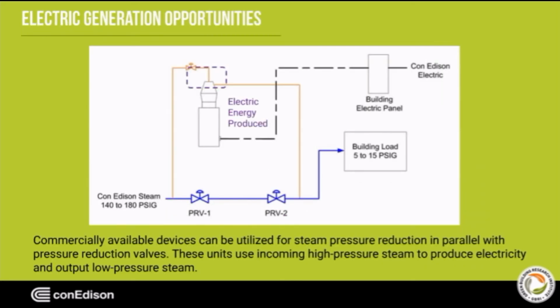As you can see here, these systems will be installed in parallel to your pressure-reducing valves. When these systems are running, the PRVs are bypassed and electric power is produced, and low-pressure steam needs are provided to the building. Overall, these systems are meant to provide customers with electric savings without impacting the operation of their steam system in any way.